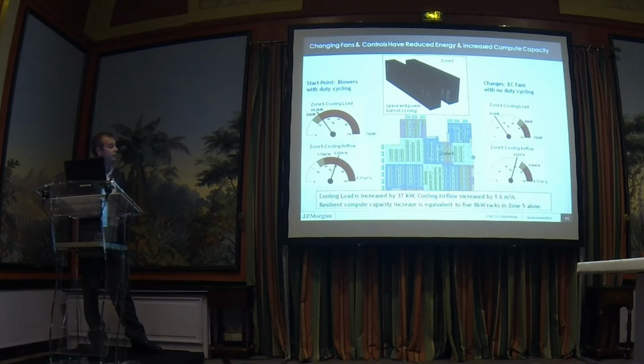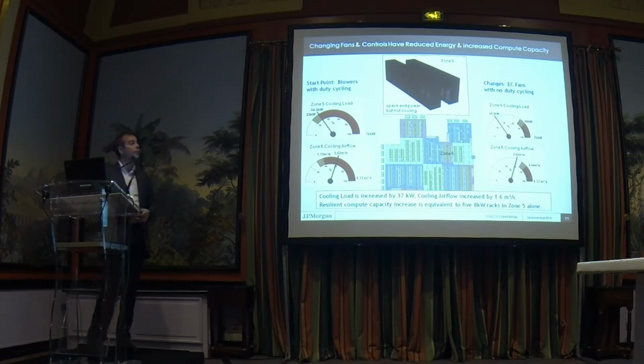So after we put the control change in, put the bigger fans in, leveled all the set points off, and got rid of the zone control on all the crack units, so we just run them continuously now, I've now got a cooling potential in that zone of 60 kilowatts. The airflow being used was 2.5, but now the potential is 3.4, 3.34. So by doing this, I was able to put an extra 37 kilowatts of load in that space, or 5 racks at 8 kilowatts each.